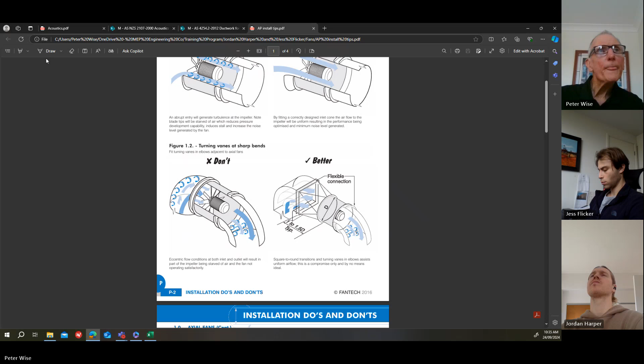So that's a pretty standard thing you'll come across in the industry. If you're using an inline centrifugal fan, you know, the box fans with inline centrifugal, we've talked about these before. It comes in a box, but it's got an inline centrifugal fan wheel inside it. You can put the flexible connections at the inlet to those. That won't affect them because of the type of fan it is, but axial fans, it's critical to get them in the right position.